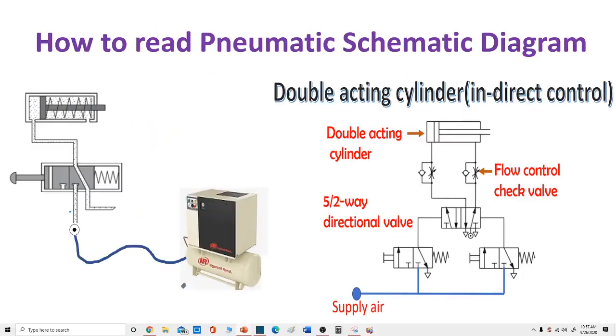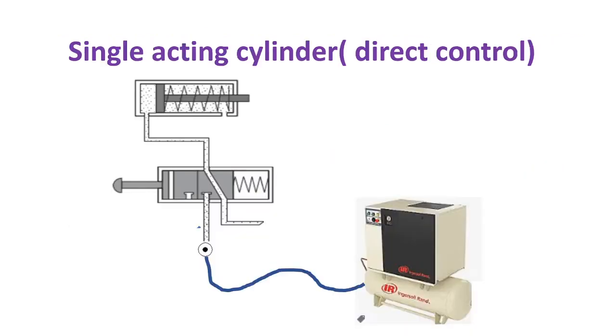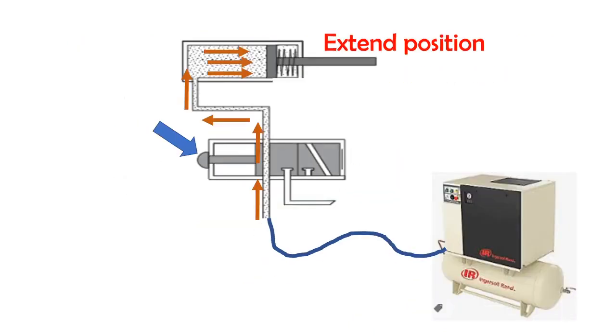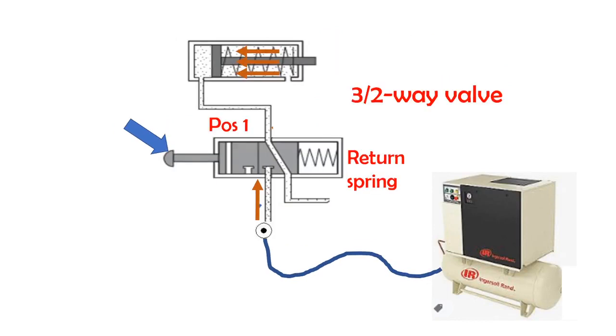Now let's look at how to read a pneumatic schematic diagram. This is a single acting cylinder: it is to advance when a push button is pressed, and the cylinder is to remain in the advanced position until you release the push button. When you release the push button, the cylinder is to retract by a return spring.